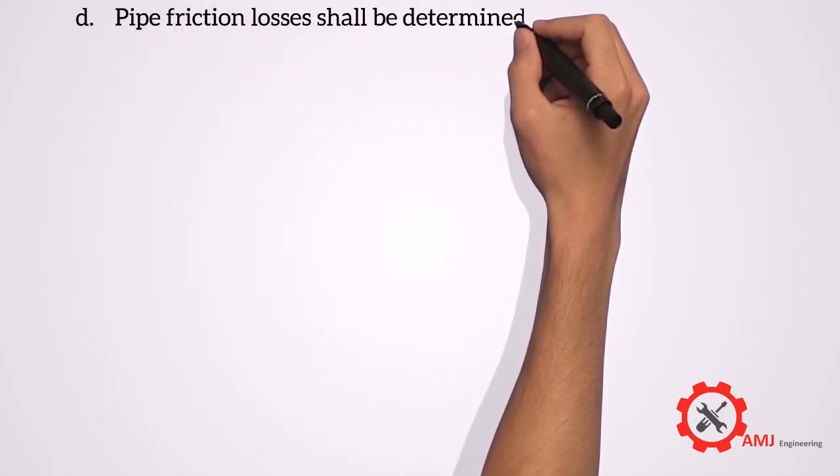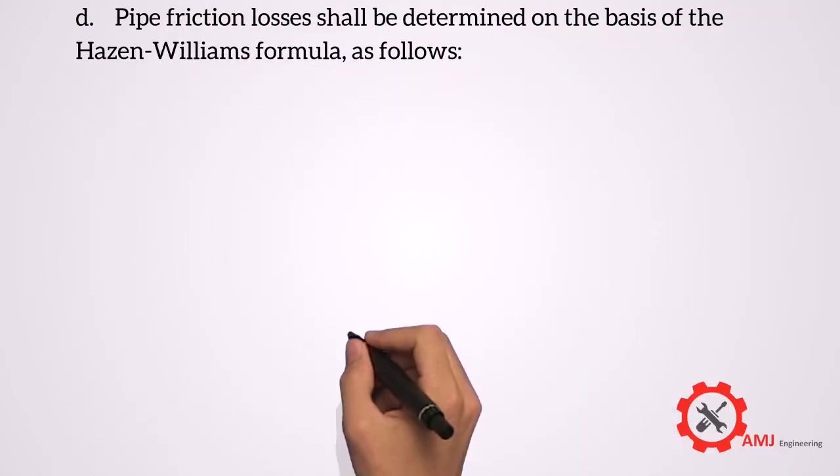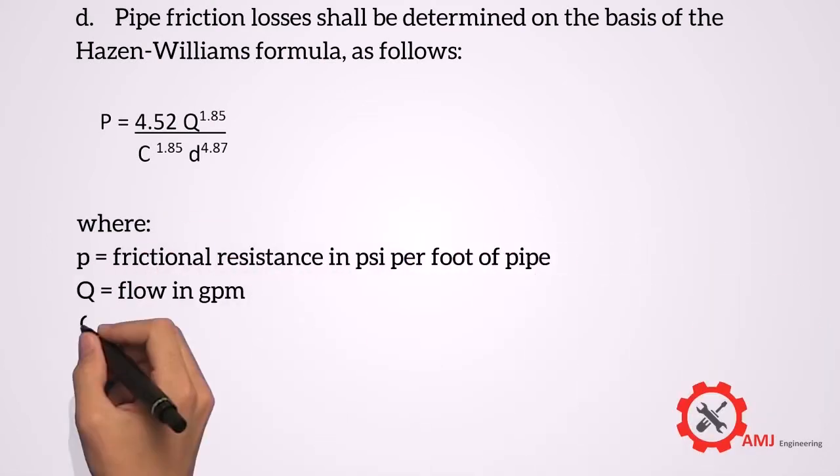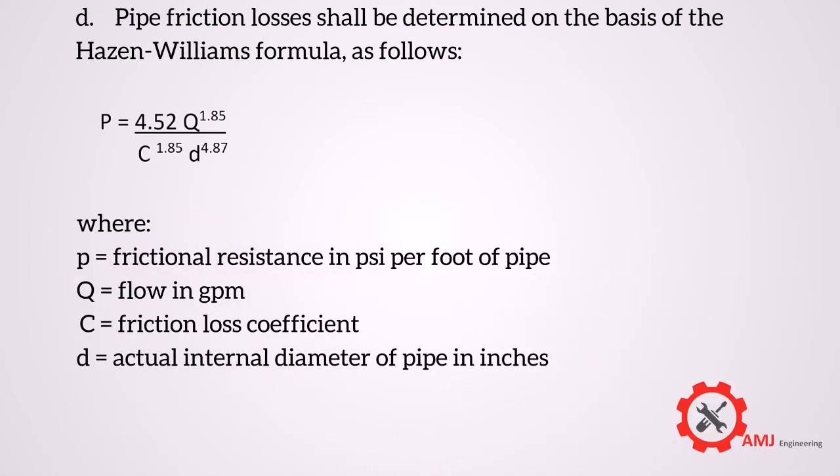Pipe friction losses shall be determined on the basis of the following Hazen-Williams formula, where P is the frictional resistance in psi per foot of pipe, Q is the flow in GPM, C is the friction loss coefficient, and D is the actual internal diameter of pipe in inches.